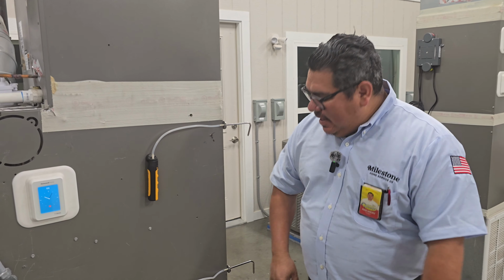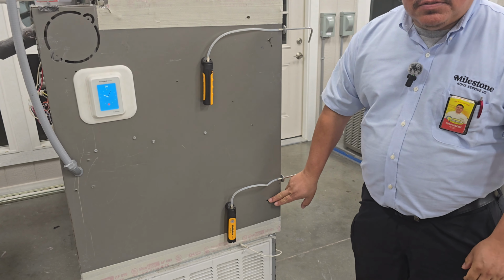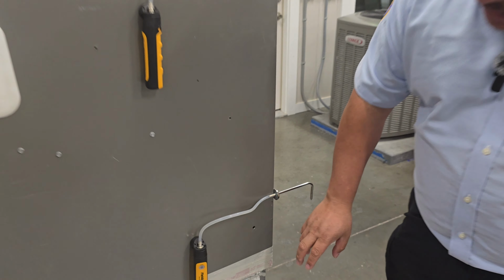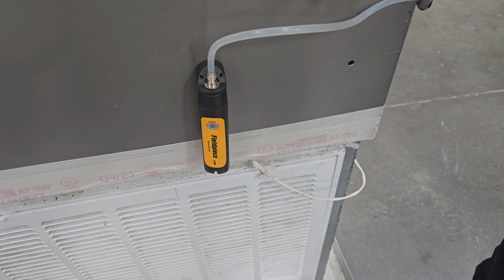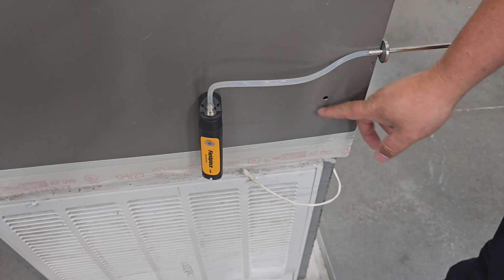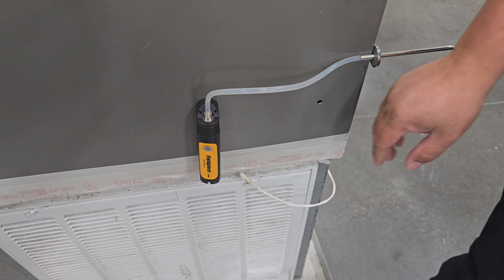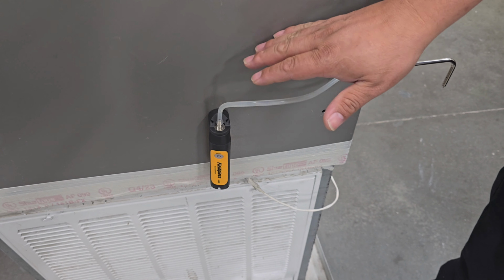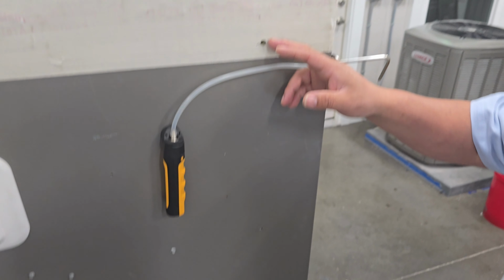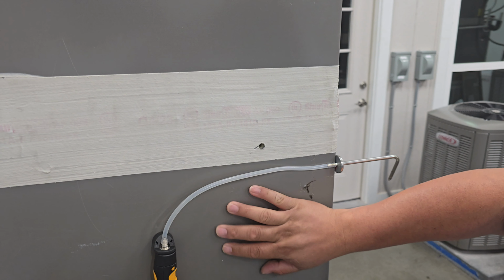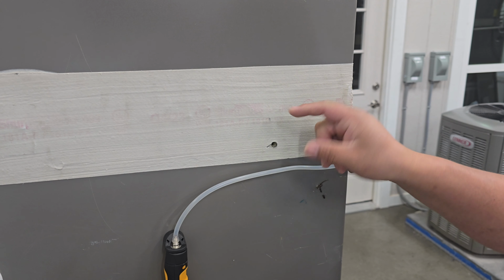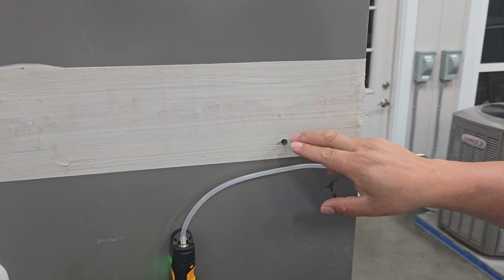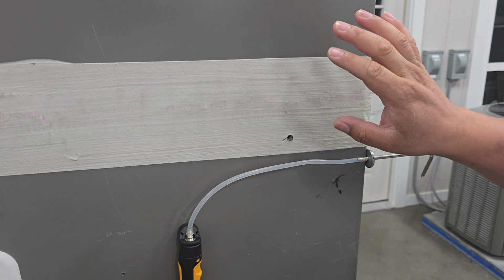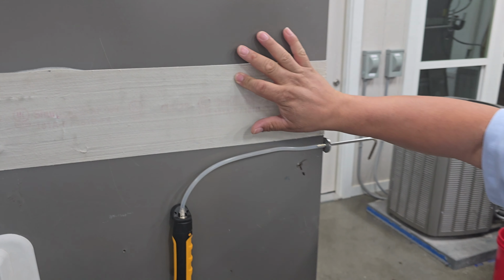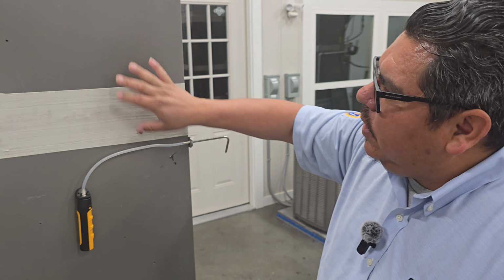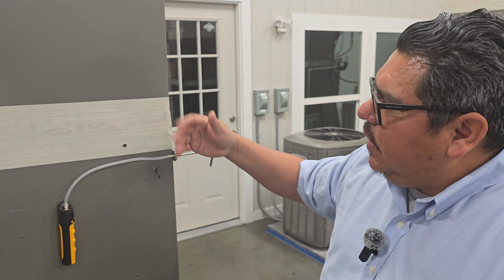So our next step is going to be drilling some access ports for our probes. The first one's going to be after the filter and before the blower motor. And you want to make sure that you have space for your probe. It's not going to hit anything. And you also want to make sure you're not going to hit the blower wheel housing. The second one's going to go between the evaporator coil and the heat exchanger. And you want it about 2 inches away from the seam. And the reason you want to go underneath is because you have the risk of hitting the drain pan or the coil. You could cause a leak either way.